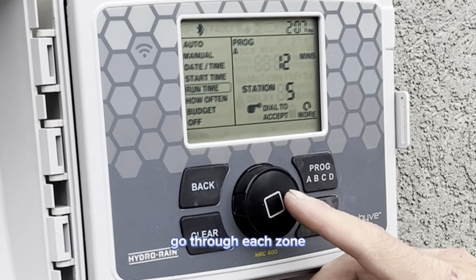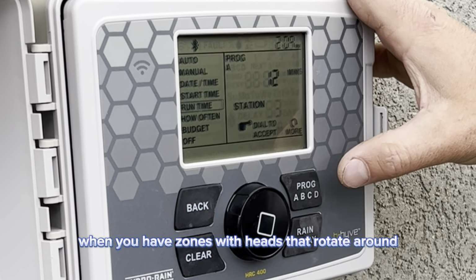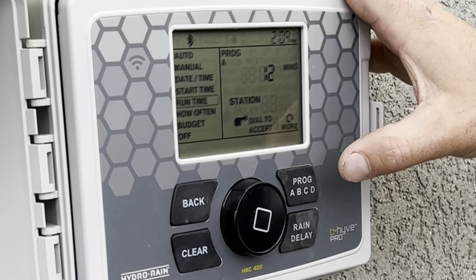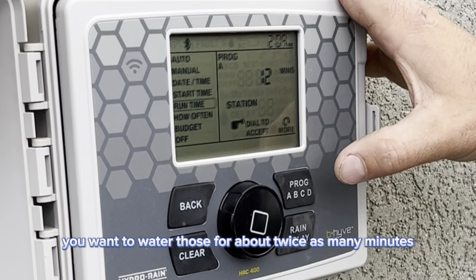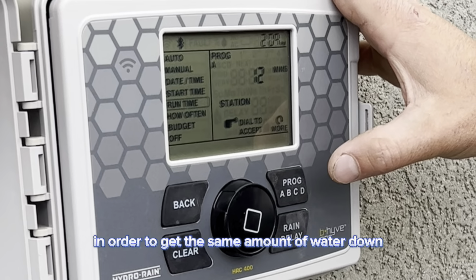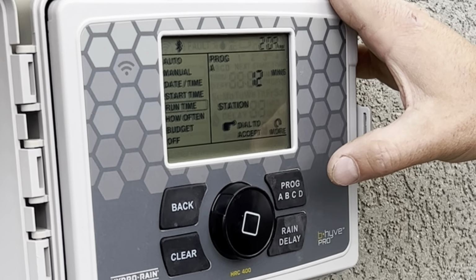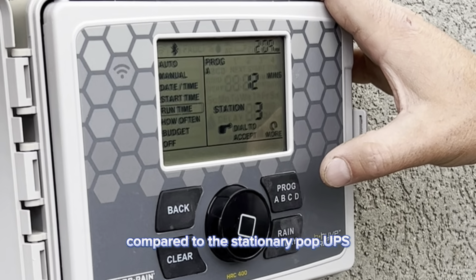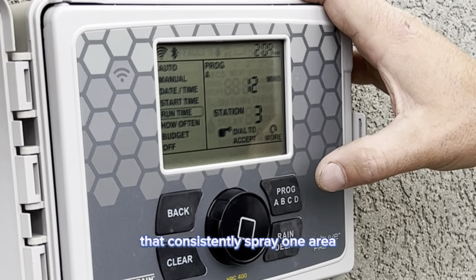Go through each zone. Keep in mind, when you have zones with heads that rotate around, general rule of thumb is you want to water those for about twice as many minutes in order to get the same amount of water down compared to the stationary pop-ups that consistently spray one area.